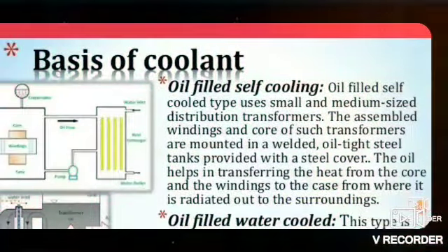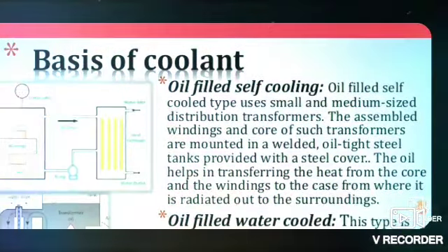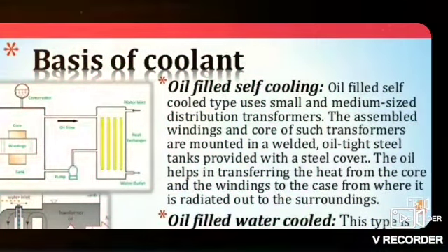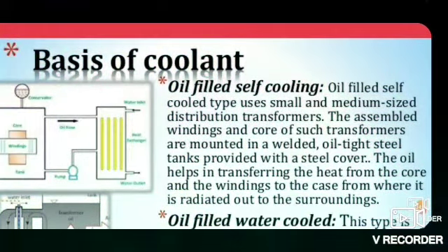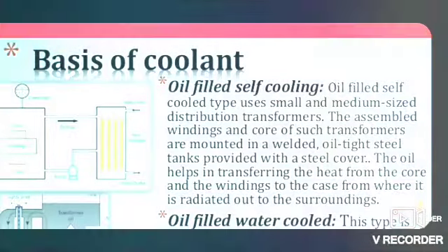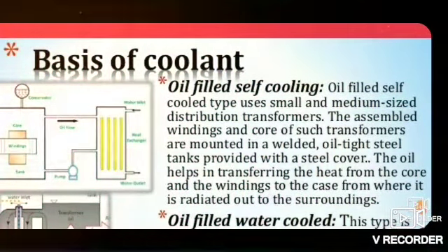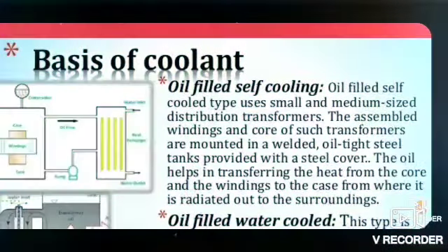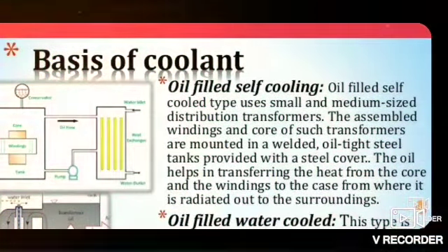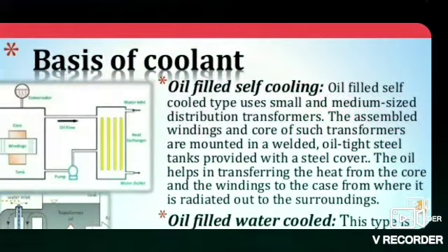The assembled windings and core of such transformers are mounted in a welded, oil-tight steel tank provided with a steel cover. The oil helps in transferring the heat from the core and the windings to the case, from where it is radiated out to the surroundings.